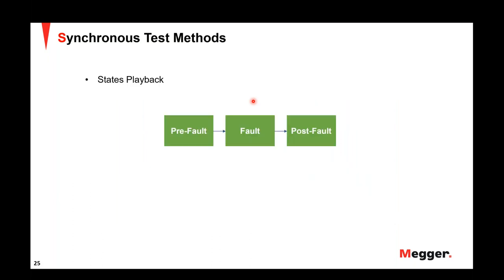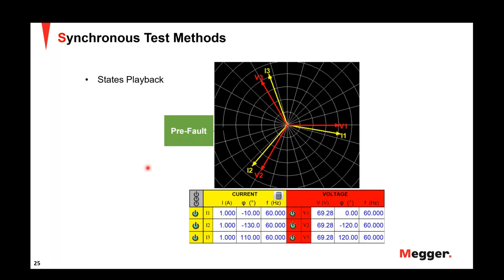So next we'll talk about different synchronous test methods that are used, right? One of them is the states playback. In the states playback, you create different states that indicate a particular power system condition, right? So there is a pre-fault state, wherein you just inject some analog quantities to these relays, which will tell the relays that it's a normal load condition on a power system, right?